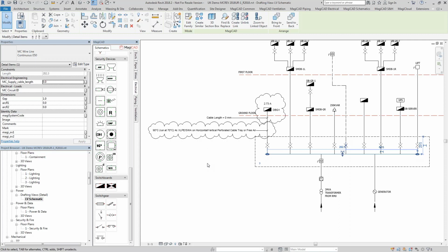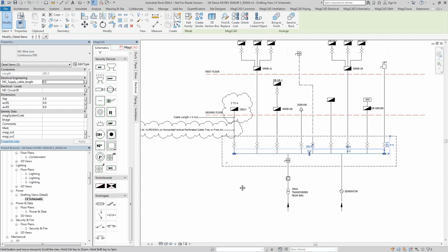But the cable packet essentially gives you a cable route that you can follow. It will automatically generate your cable length based on the actual route that follows your containment, and then you can also tag it to show how many circuits you have attached to it, what those circuits are, what their circuit references are, what the cable types are, and so on. You can load it up with all kinds of data. So again, we'll have a separate webinar on the actual cable packet and how that works.